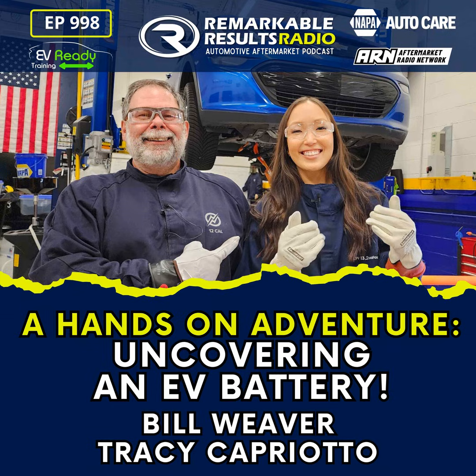Now, while most manufacturers out in America right now do not force technicians to put this type of equipment on, other parts of the world that have higher standards for safety not only recommend, but require that we put arc flash protection of at least a level number 2, and we can talk about that in some future classes, but we need to make sure that we're protected the whole time that we work on an exposed battery pack. A lot of this has to do with the National Fire Protection Code.